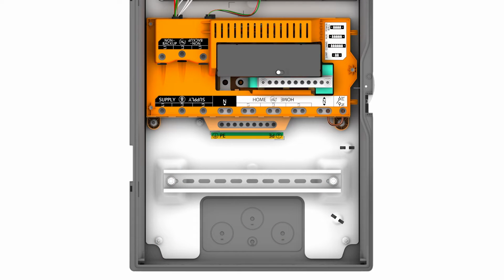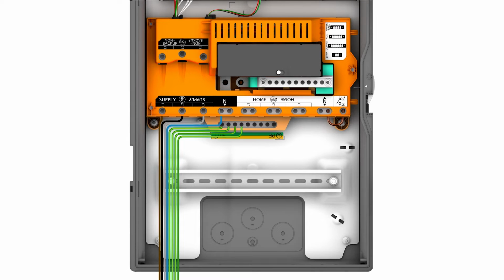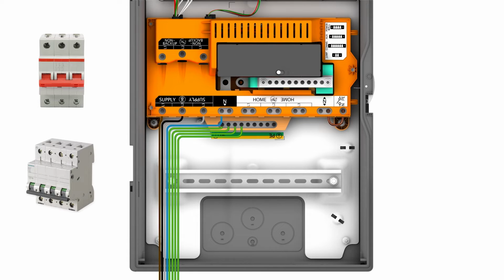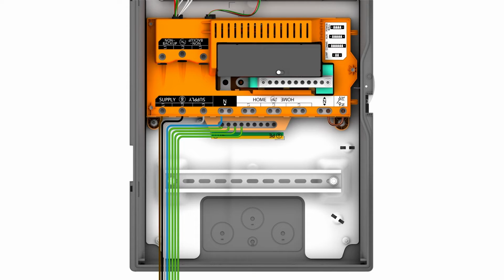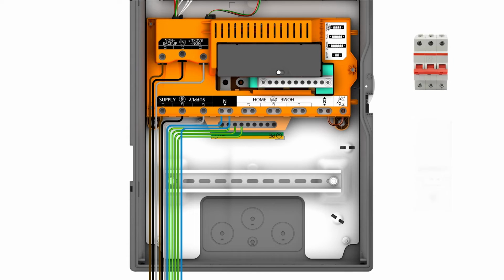For three-phase systems, land the incoming Line 1, 2, and 3 and neutral conductors on their respective ports at the black supply label. A 3 or 4 pole overcurrent device for the service feed can also be installed on the DIN rail if not already installed before the gateway. Any three-phase loads or three-phase solar inverters must be connected to the non-backup terminals. Three-phase loads and three-phase solar inverters cannot be included in the backup circuit.